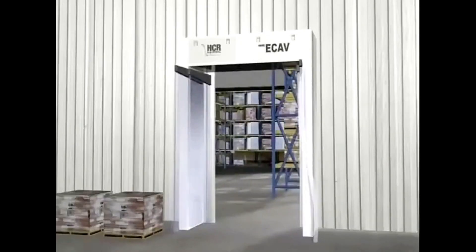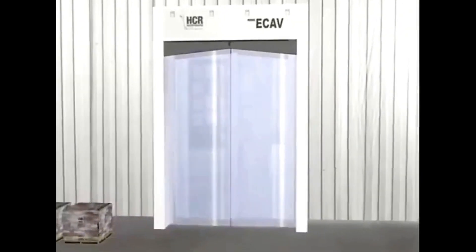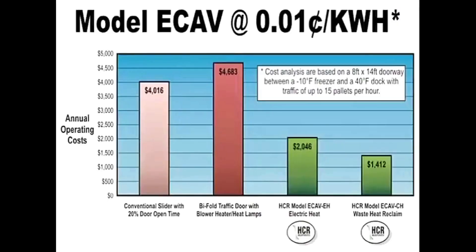Some HCR units can optionally utilize a waste heat reclaim system, making use of the plant's refrigeration waste heat, a by-product of cooling. When using waste heat reclaim, annual operating costs are significantly reduced. The amount of heat that is required depends on the doorway size, model selected, the type of refrigerant, and the levels of temperature and humidity existing on each side of the opening.